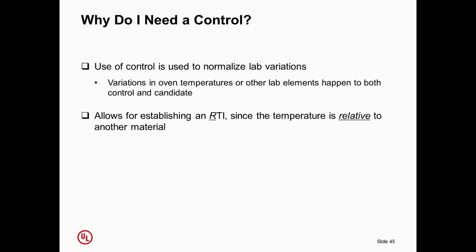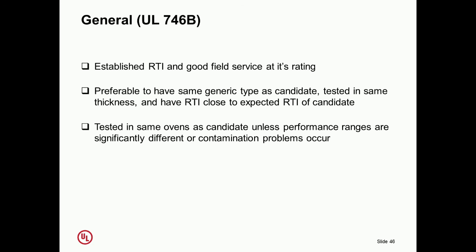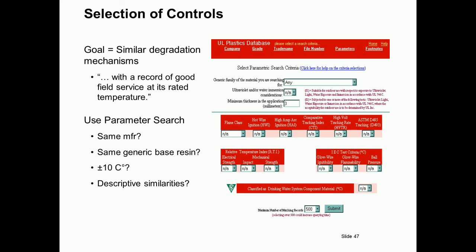We talked about relative thermal index. There's a control that we use for that testing. We're looking at a relative measurement to another material, so we'll be very careful on the selection of a control and comparison. In general, we use 746B as our test method. We use it because there's a lot of data going back many years on RTIs and a large material database. We can start to do these evaluations quickly. We don't have to go to the full 10,000 hours, or in some cases maybe up to 100,000 hours of actual multiple point measurements. We can do it by comparing to known materials.